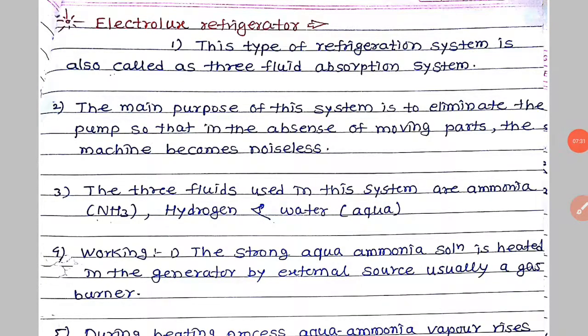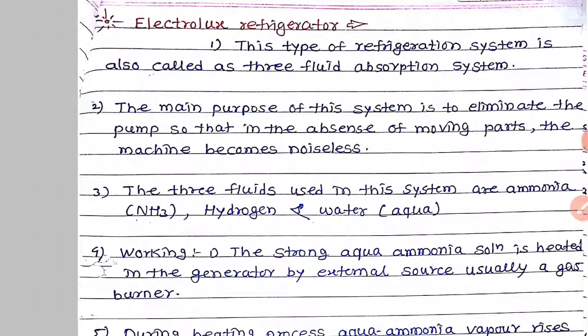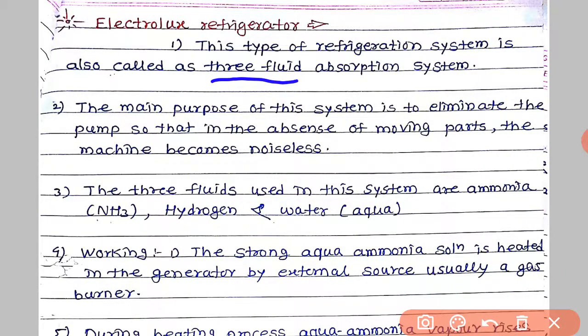Now see here, this type of refrigeration system is called a 3-fluid absorption system. Why is this a 3-fluid system? Because there are 3 fluids, which are ammonia, hydrogen and water. 3 fluids are used in this system, so this is called a 3-fluid system. So what is the main purpose? The main purpose of this system is to eliminate the pump, so that in the absence of moving parts the machine will be noiseless. The pump has moving parts inside it, so in the absence of the pump the system will be noiseless. So we have to avoid the use of a pump to make the system noiseless.